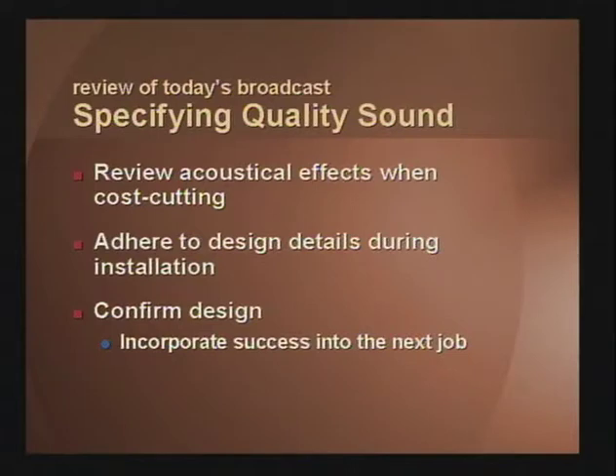Also, take a look at reviewing the acoustical effects when you're building the job. Once the design is locked, you might run into issues of cost cutting, sometimes called value engineering. These items can inadvertently take out the noise control options you worked to put in. Make sure they stay in the project. Adhere to the design details during the installation. Make sure that what you design goes in that way. Sticking a post right off a fan discharge and then rerouting the duct around that post mechanically works, but acoustically, frankly, it's often a disaster. And then finally, confirm the design success. As you have successes, and you will, incorporate those successes into your next jobs.